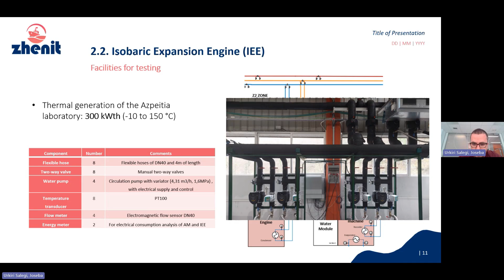Following with the testing matrix, we have 4 variables when we decided to start with these testings. 2 of them are the supply temperatures of the water in the condenser and in the evaporator that we decided to define in this way: we have the fresh water at 20, 30, and 40 degrees, and the heat source is at 80 and 90 degrees. Apart from that, we decided to put the feed pump frequency at 30% all the time. This frequency is the velocity we are giving to the motor that supplies the oil power pack, which at the same time supplies the feed pump. And lastly, we have the valve that gives us this pressure difference.